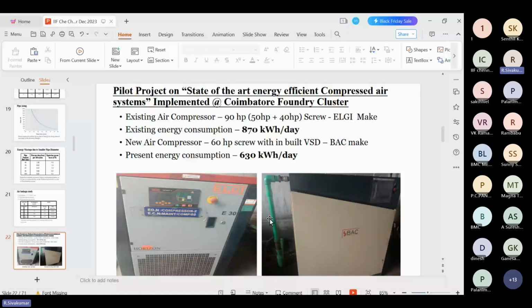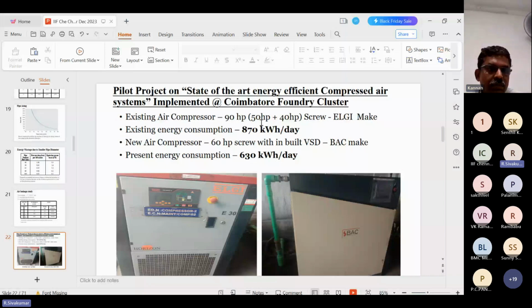In the existing system, there were 90 HP, 50 HP and 40 HP air compressors adopted. Both compressors run for almost 16 hours, and one single compressor runs for 6 to 8 hours in the night timing only. Both the compressors are screw compressors only. The existing energy consumption is around 870 units per day.